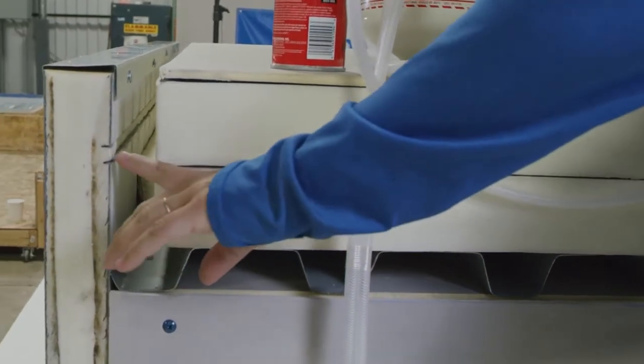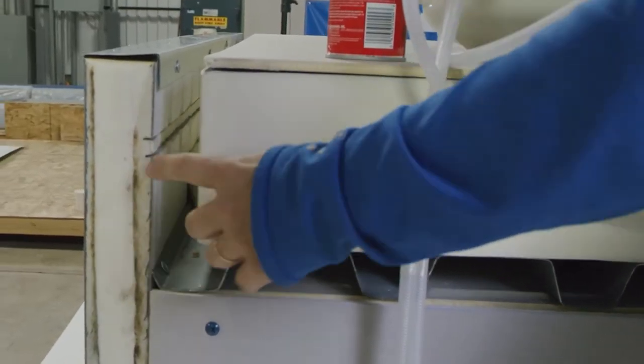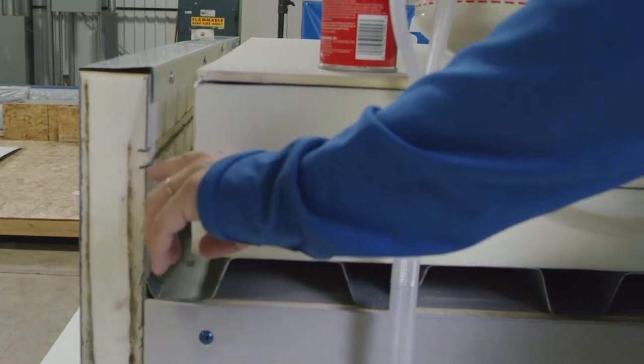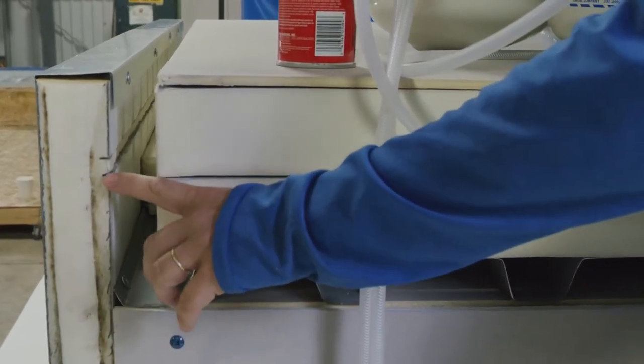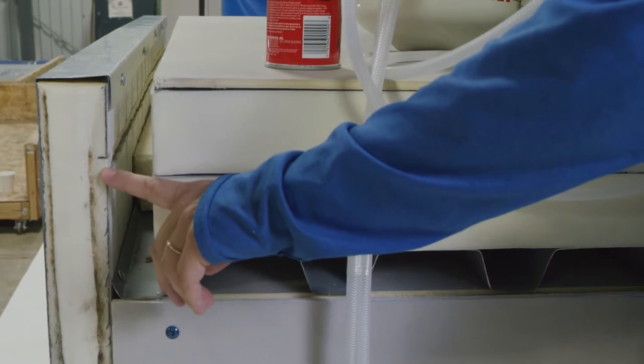And then you can see in here, this is what we call a thermal break. What we've done is we saw cut the metal on the outside of this insulated panel. And what that does is it keeps cold air or cold energy from traveling all the way out to the outside of the building.